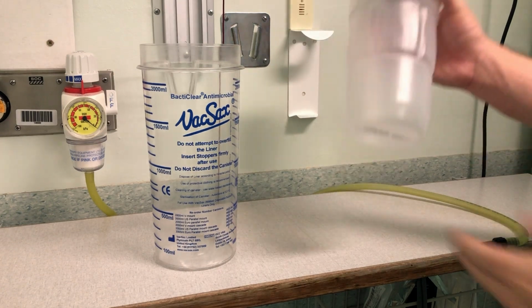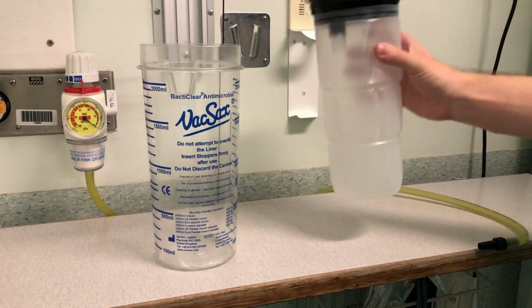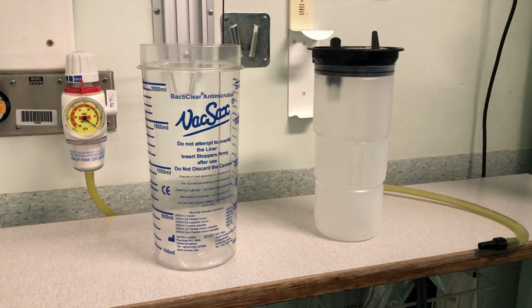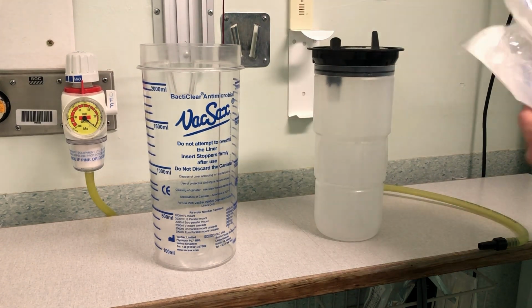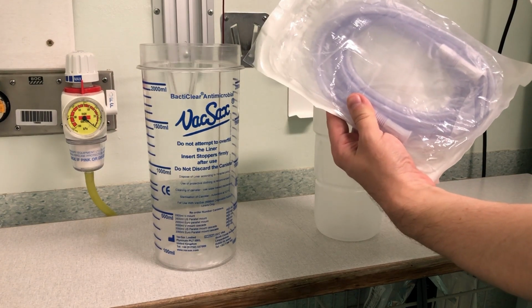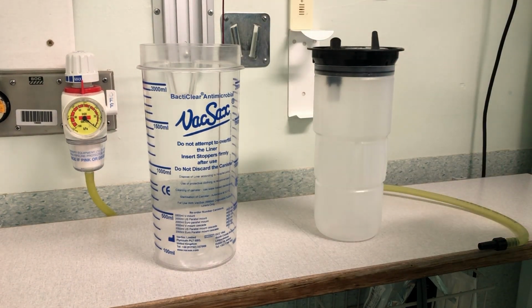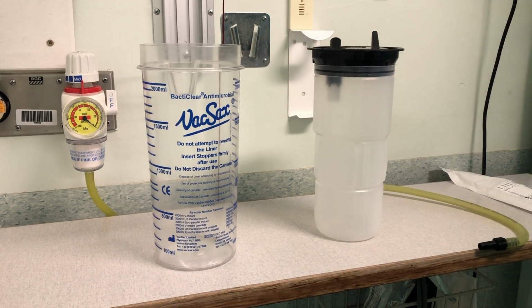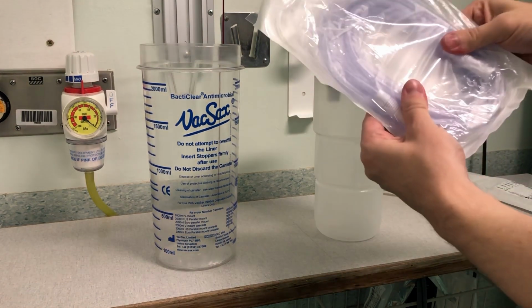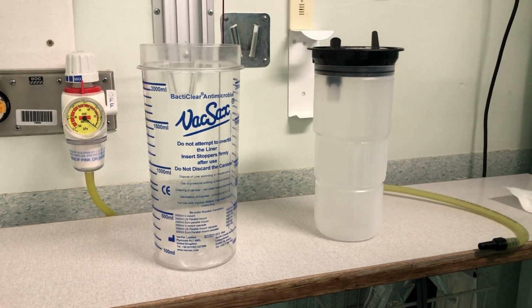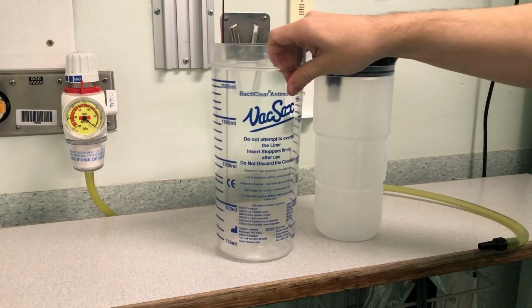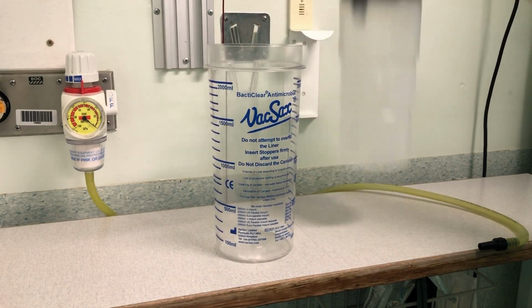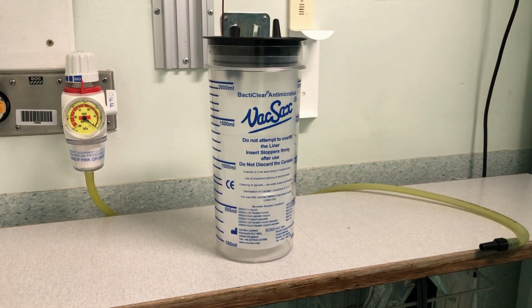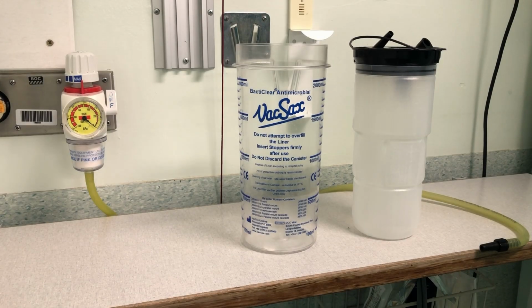Then on to the disposable parts. The Vacsax Bacti-Clear suction liner, 1 litre, 2 litre and 3 litre, depending on canister size, and the patient suction tubing and yankers or suction catheters. The disposable parts must be replaced after each use. For infection control purposes, the suction tubing should remain in its sterile packaging until required. And note that the device is limited by the canister volume and liner volume. Ensure that the correct liner is used within the canister. If it is not, you can still use it, just be aware that you're going to have a much smaller capacity than expected.